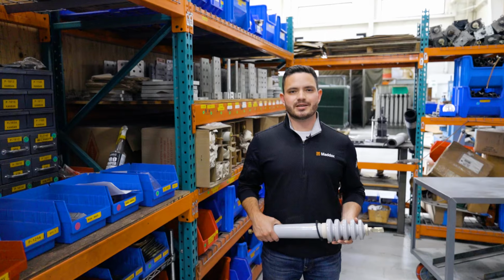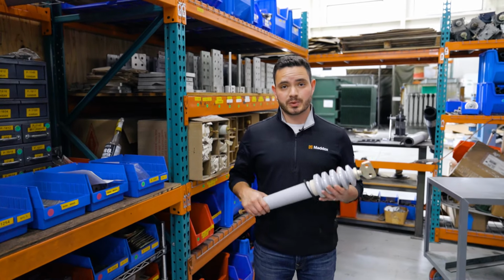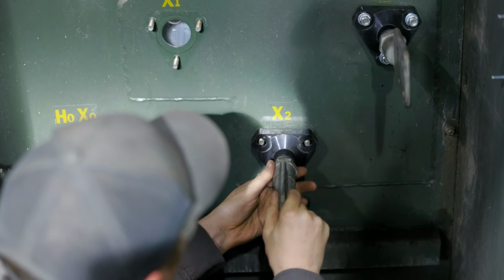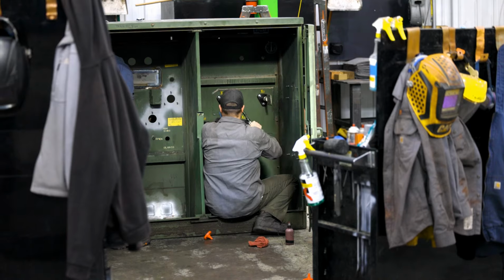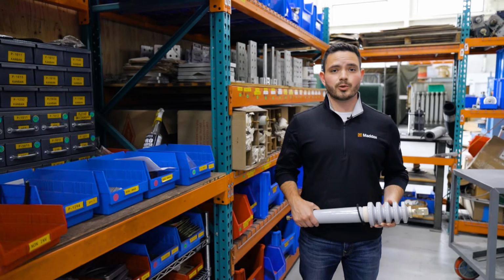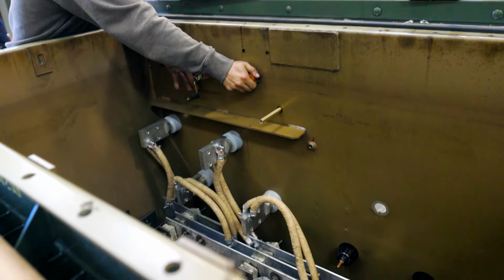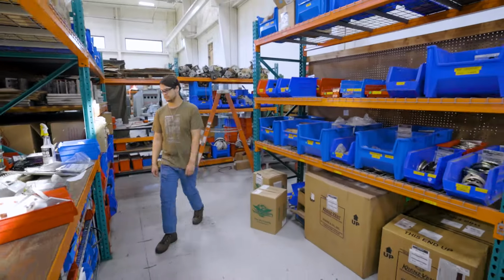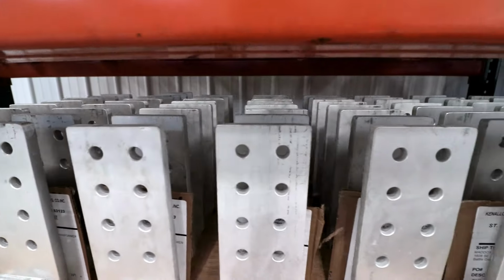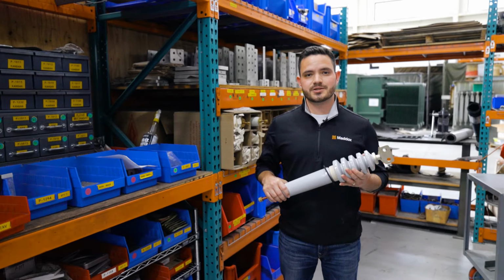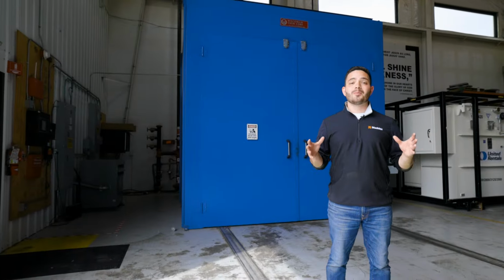Now we begin the reassembly process, which starts with replacing the components. If the old ones work just fine, we'll reuse them in the rebuild. But if they're old or broken, we'll replace them with new. Every gasket gets replaced during this process, and we keep several years worth of transformer components on the shelf to avoid supply chain disruptions. Next, we put the core and coil back in the tank.